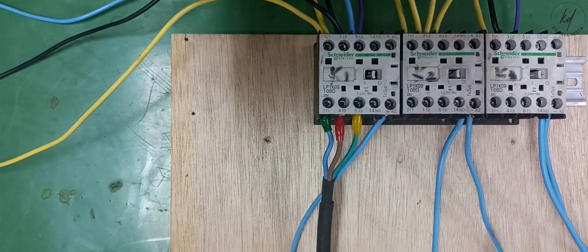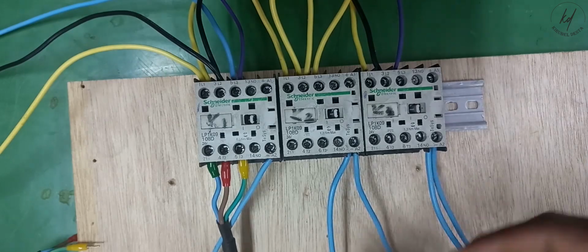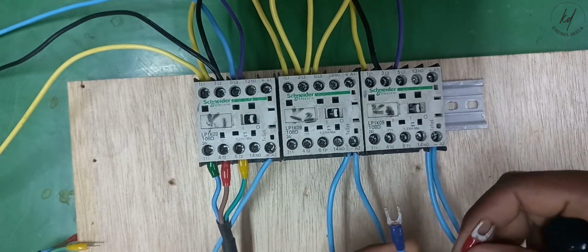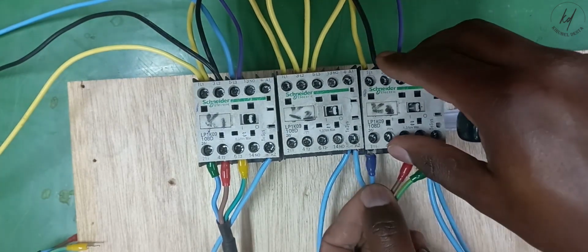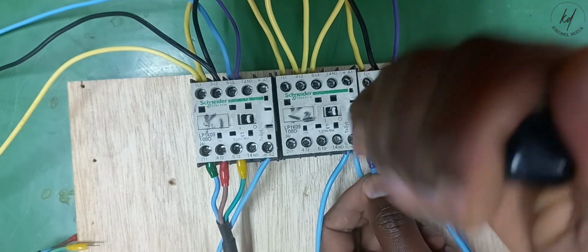This way, a Star Delta starter can only be used for light load during starting of the motor. Otherwise, the heavy load motor won't start due to low torque, which is needed to accelerate the motor to rated speed while converting to the Delta connection.